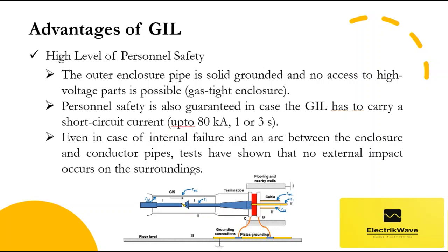GIL has a high level of personnel safety. The outer enclosure pipe is solidly grounded and no access to high voltage parts is possible due to the gas-tight enclosure. Personnel safety is also guaranteed in case the GIL has to carry a short circuit current of 50, 63, or 80 kiloampere, up to 1 second or 3 seconds. Even in case of internal failure and an arc between the enclosure and conductor pipes, tests have shown that no external impact occurs on the surroundings.